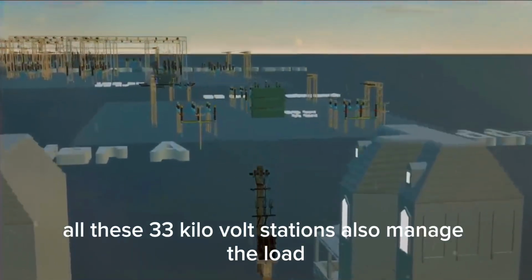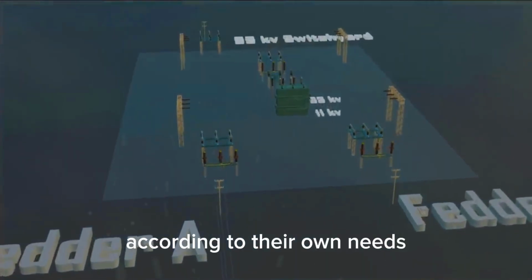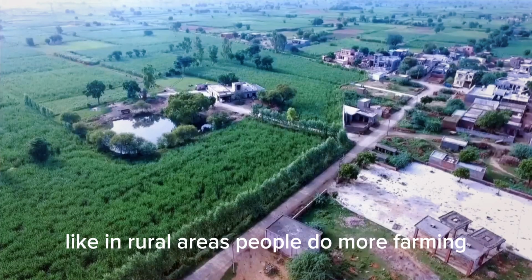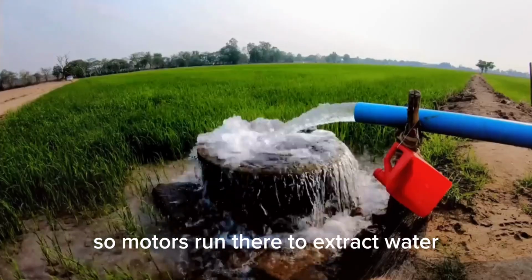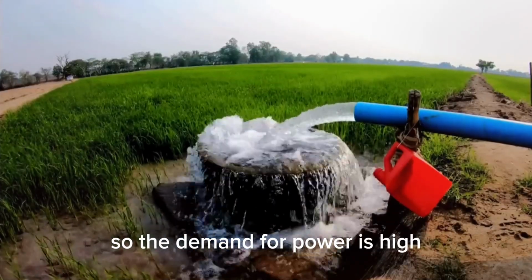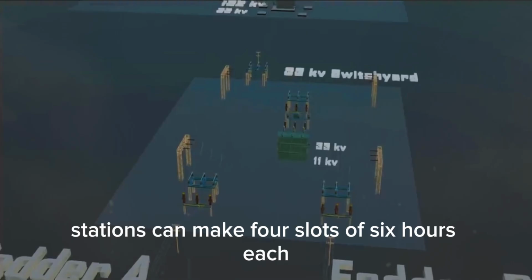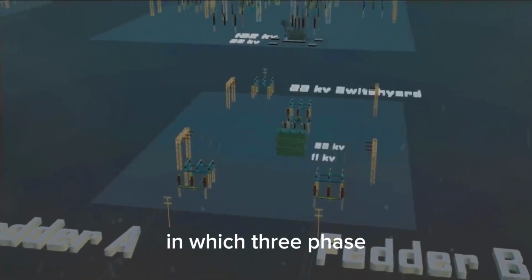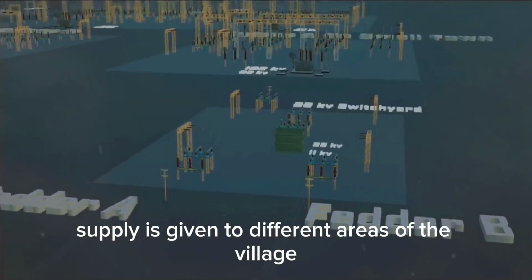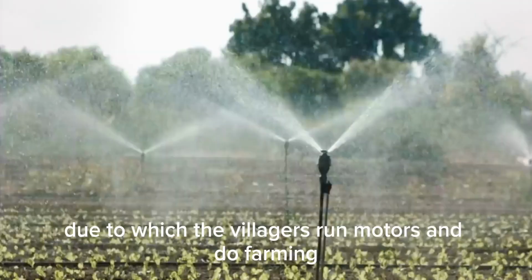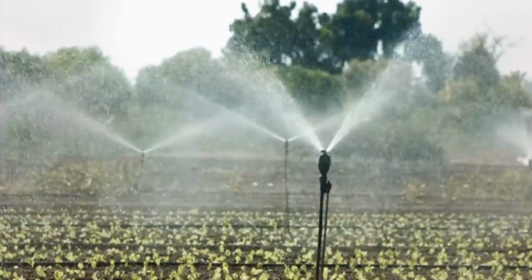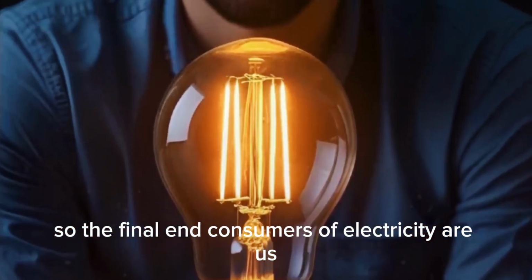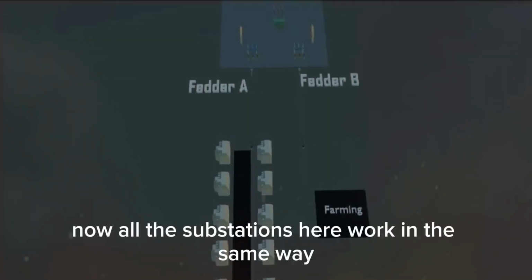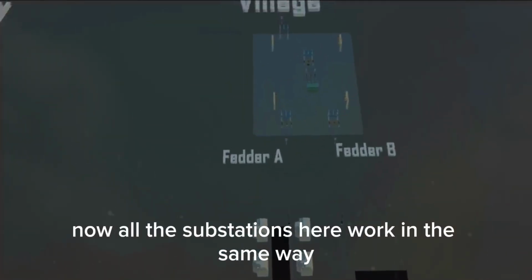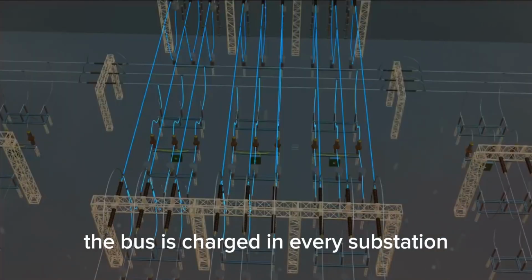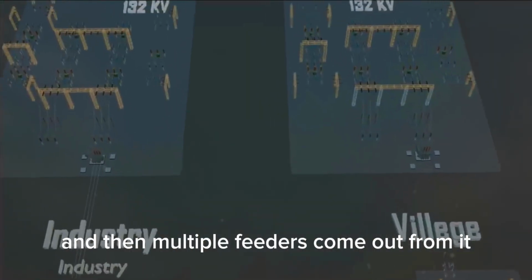Now all these 33 kV stations also manage the load according to their own needs. Like in rural areas, people do more farming, so motors run there to extract water, so the demand for power is high. So all these stations can make 4 slots of 6 hours each, in which 3-phase supply is given to different areas of the village at different times, due to which the villagers run motors and do farming. So the final end consumers of electricity are us. Now all the substations here work in the same way. The bus is charged in every substation and then multiple feeders come out from it.